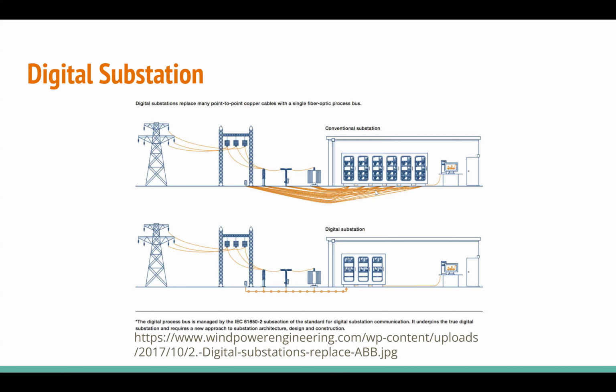The difference is, instead of doing the analog to digital conversion inside the control house like in a conventional setup, you're now doing it out in the yard. So you need specialized equipment out there. That is a cost concern for sure, but theoretically it should be offset by the savings of just using a single digital line.